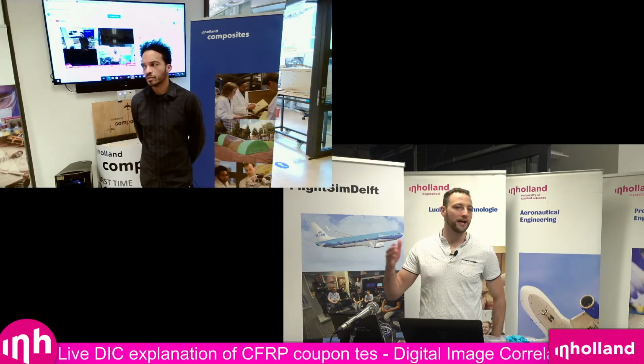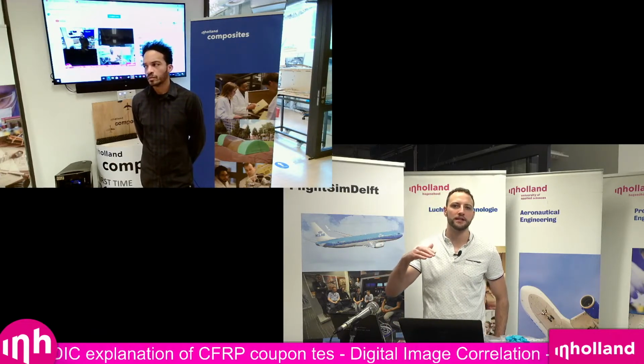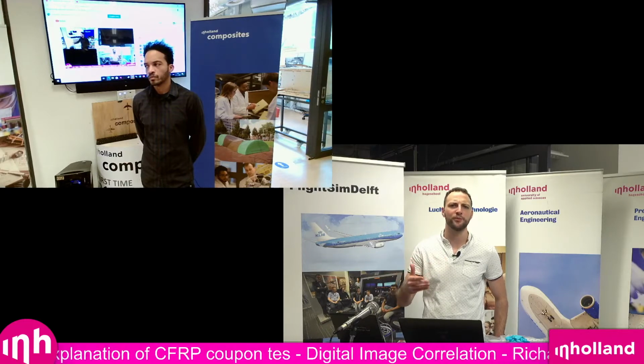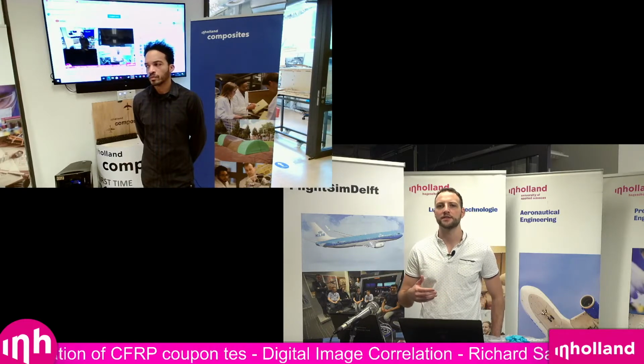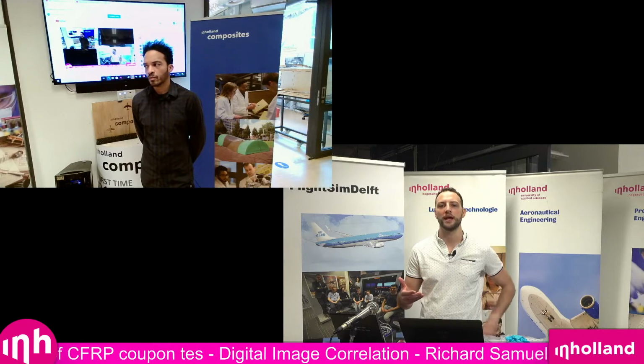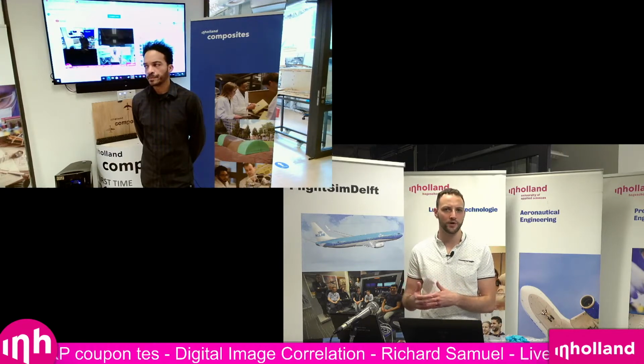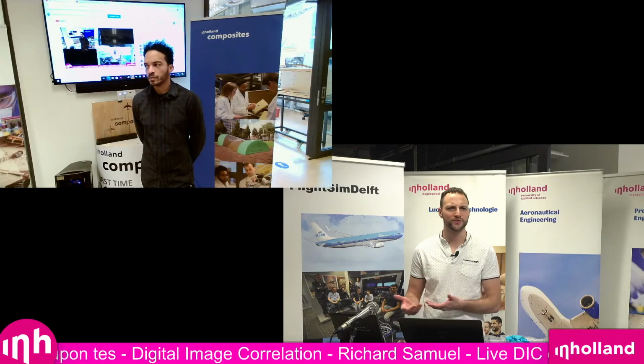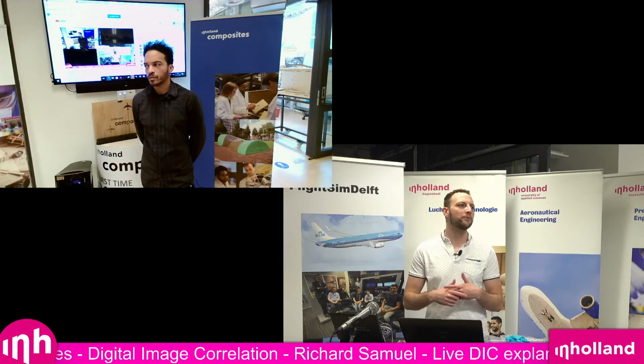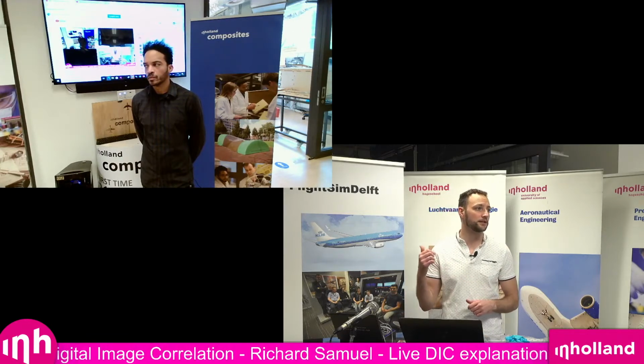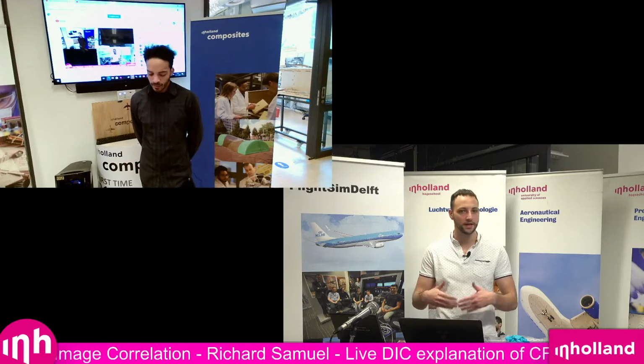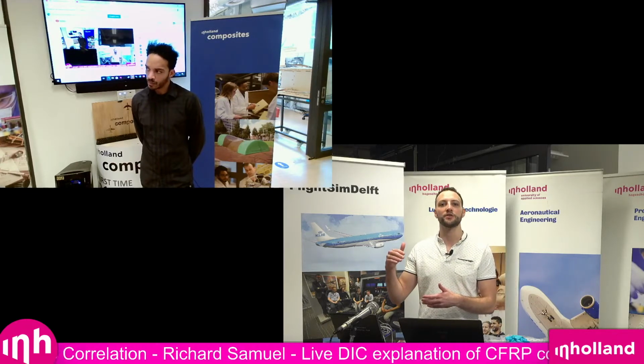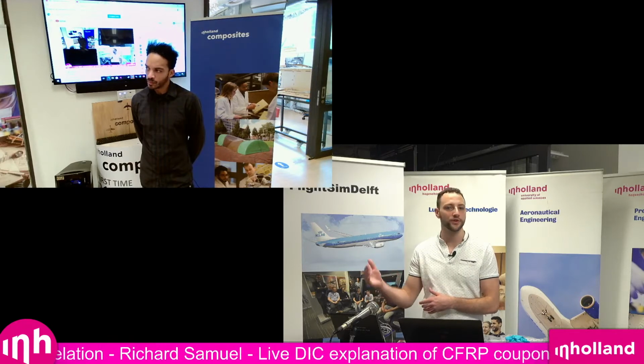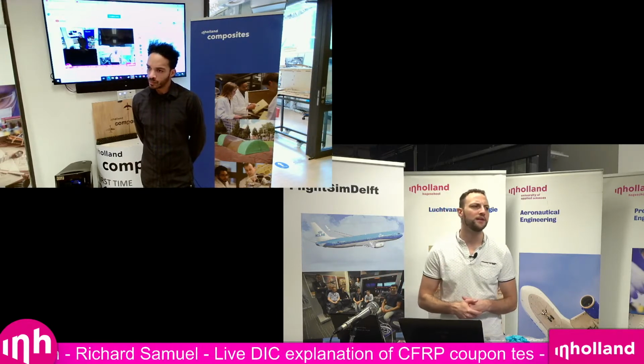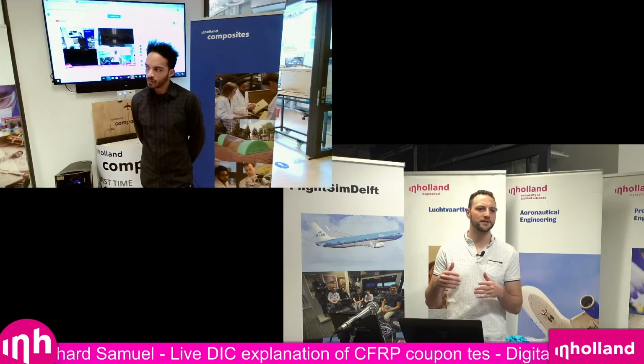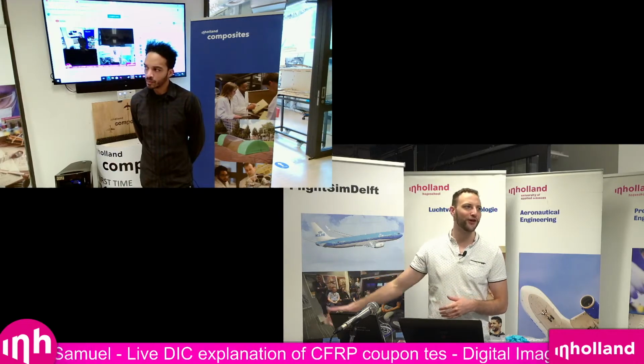The toolbar that I use to create the extensometer or the surface components or whatever it is, there's a lot more that the system can analyze, whether it's the Poisson's ratio, or if you're actually able to correlate the test bench force with the images itself, you can start to do actual stress analysis across the whole sample. So there's a lot. It's a young technology that can be explored a lot, I would say.